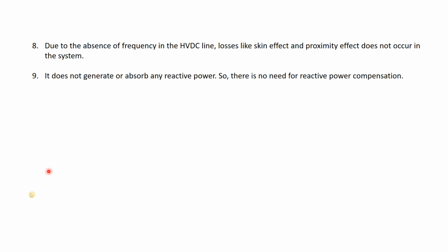So when the AC, that means the HVDC transformer, is stepping up the voltage, and then it is rectified to DC, and then the transmission starts till the receiving end, where the DC needs to be converted into AC again. Over there we will have a reactive power compensation device. But in between, in HVDC transmission, there is no requirement of these reactive power compensation devices. But in AC we have to use reactive power compensation devices in between transmission also.